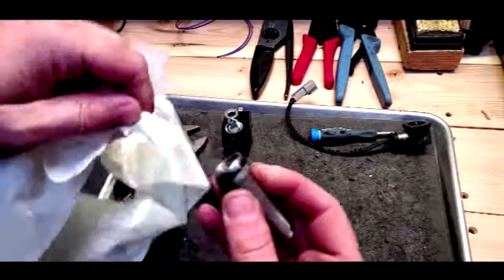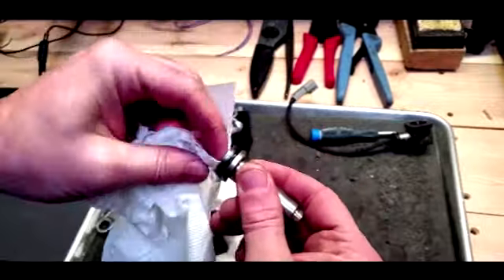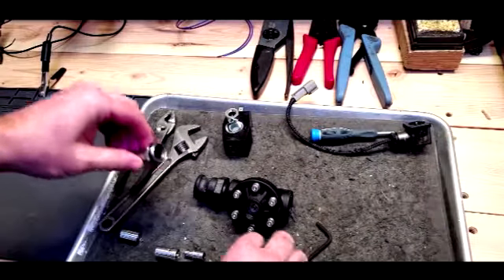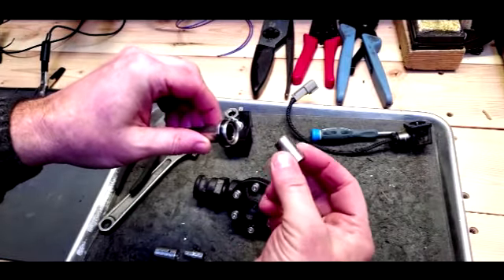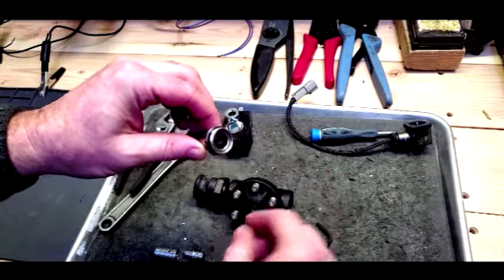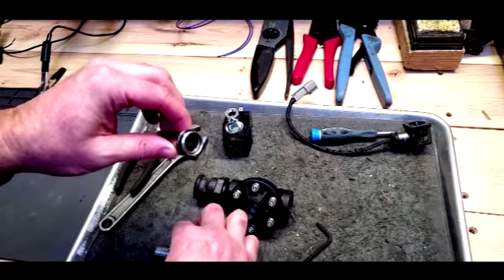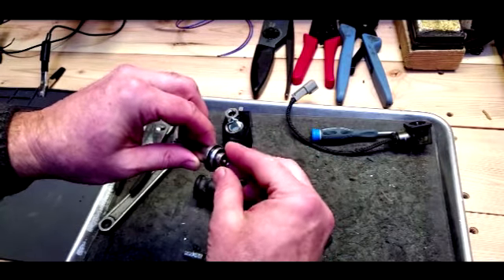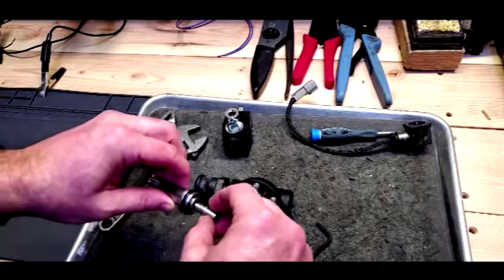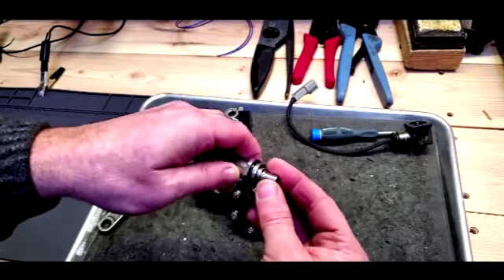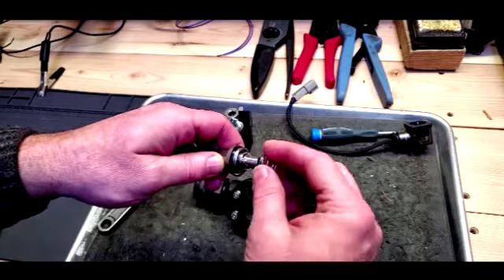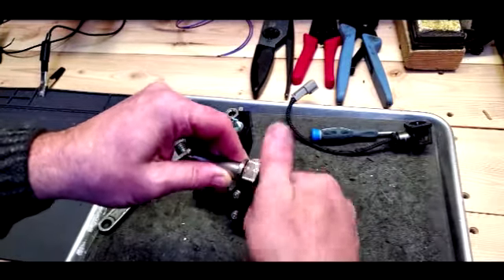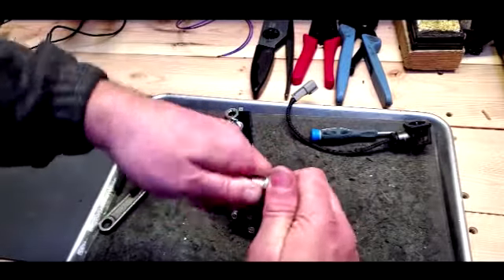Once the system is ready to go back together, we're going to clean everything up first - make sure it's good and clean. Once your components are clean, we're going to go back together here. The first piston rod goes in, and then the secondary piston goes in with a little driver. Make sure all those holes and orifices are cleaned out as well. This little piston rod itself will go in, and then we do the spring, and finally the hex nut over the outside. Make sure your o-ring is installed there on the end of the flange.